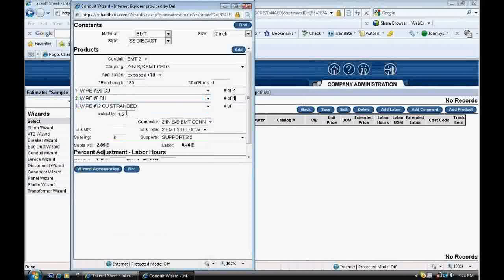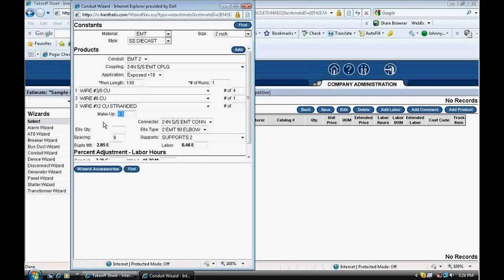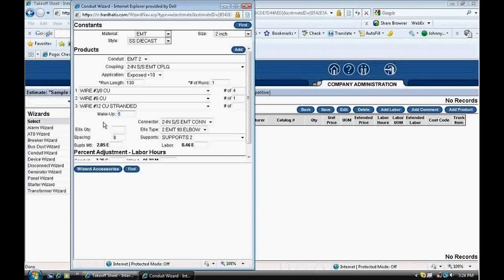Next, I input the makeup length. This, as I explained earlier, wire makeup is the amount of wire to be added that extends past the end of the conduit to the termination point. The conduit wizard calculates the amount of wire sticking out of both ends of the conduit. The quantity is entered into the makeup box. In this example, I enter 5 feet, or just a 5 there, and 5 feet of all wires will be added to the estimate for both ends of the conduit run.